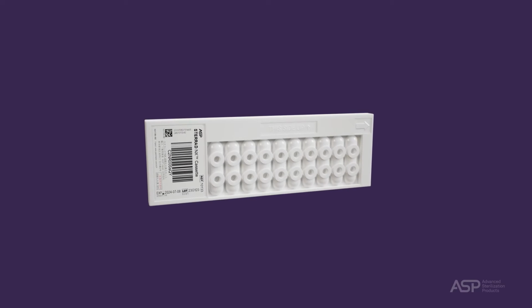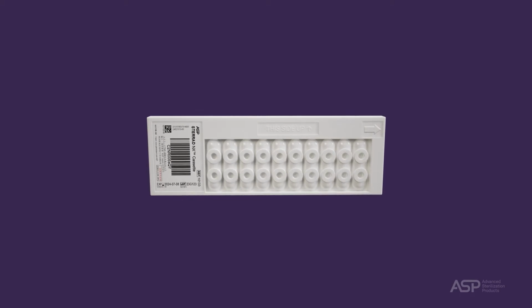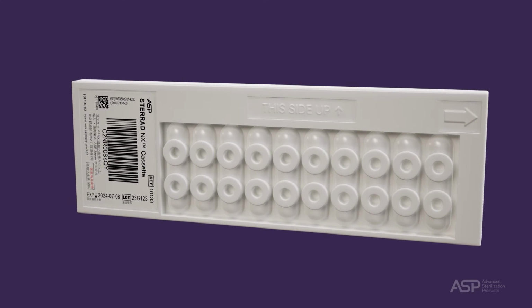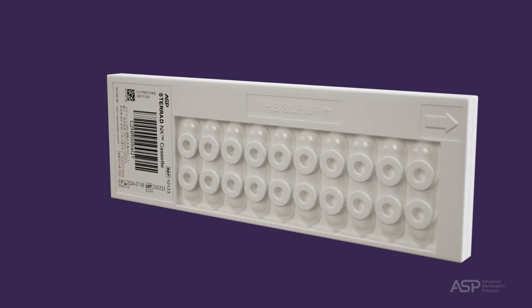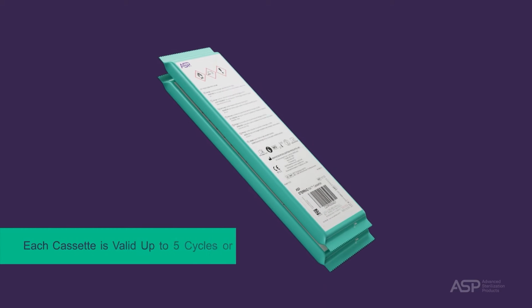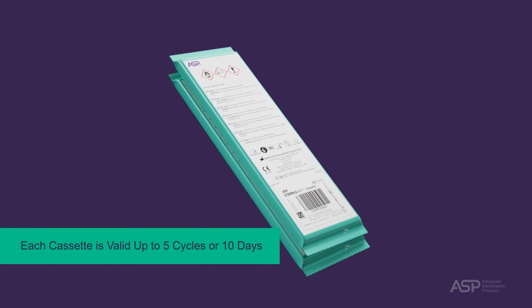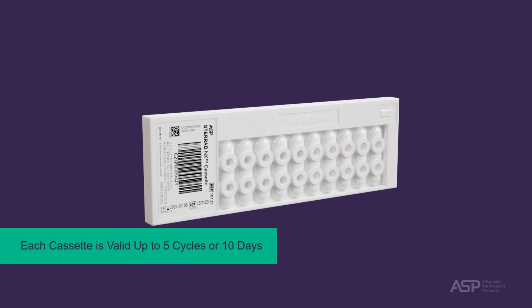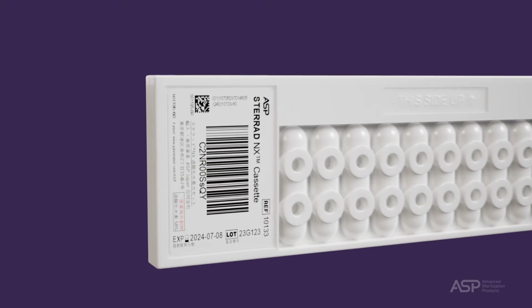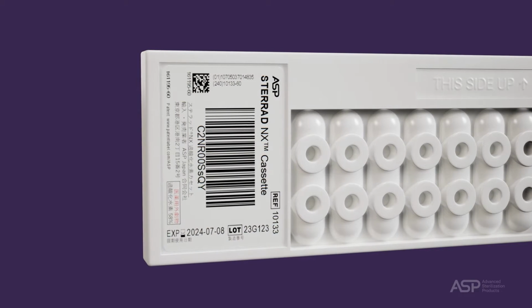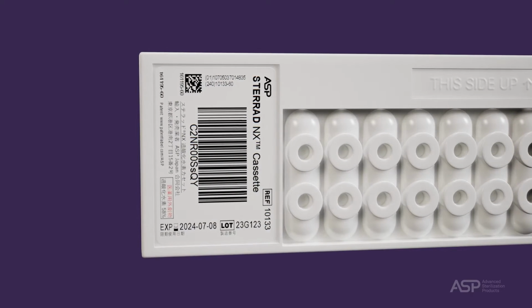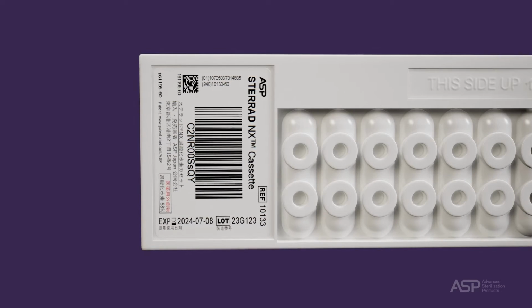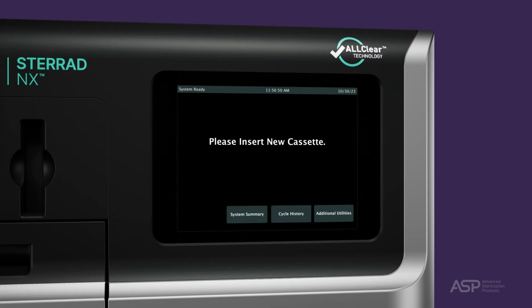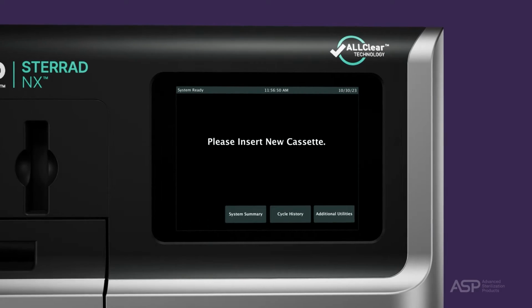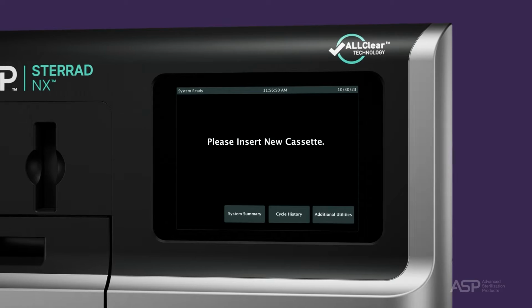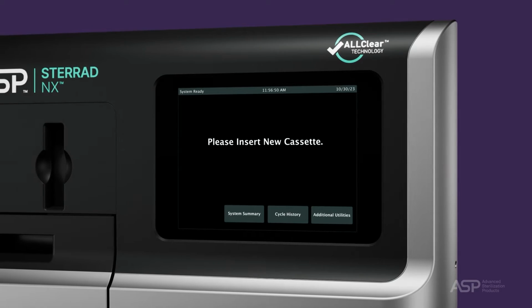Let's discuss the sterilant cassette that is used in the STERRAD NX sterilizer. The cassette contains 10 sealed capsules of 58% hydrogen peroxide solution. There are 2 cassettes per case. Each cassette is valid for up to 5 cycles or 10 days. The use of the cassette in the STERRAD NX sterilizer is controlled by a printed barcode. The barcode limits the use of a cassette to the appropriate sterilizer and ensures cassettes are not used beyond their 12-month shelf life. The screen will display the message, "Please insert new cassette," if a new cassette is required, if the cassette in the sterilizer is expired, or if there is no cassette installed in the sterilizer.